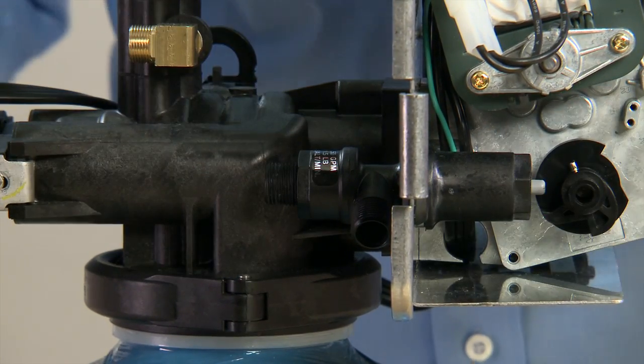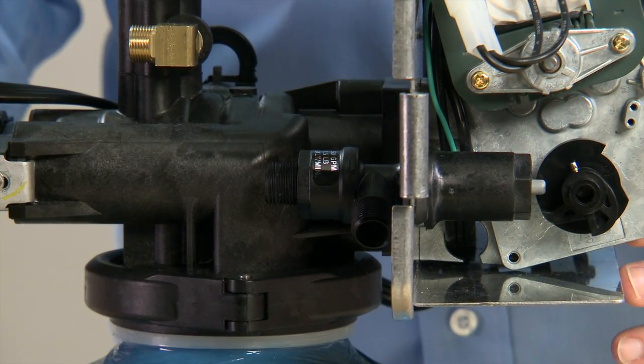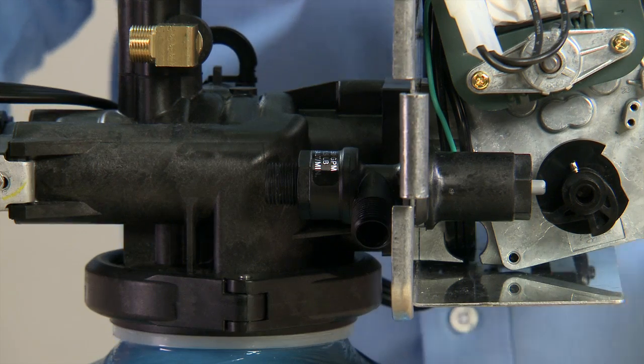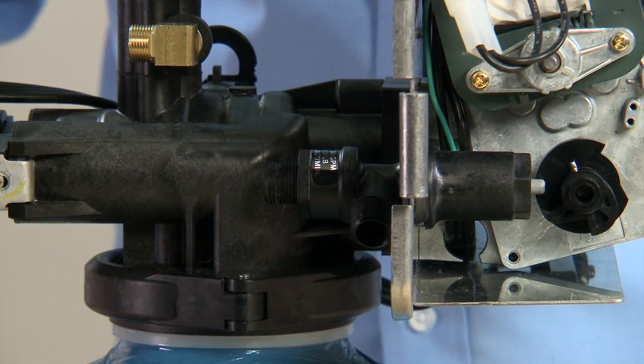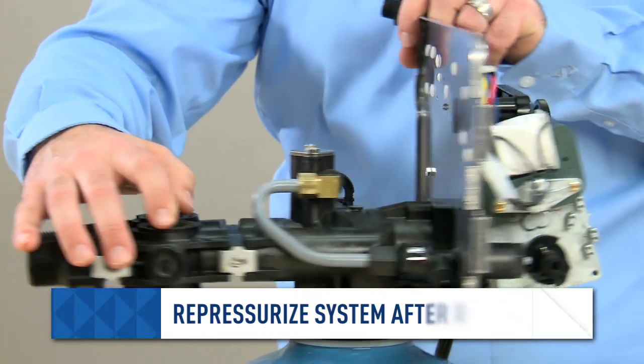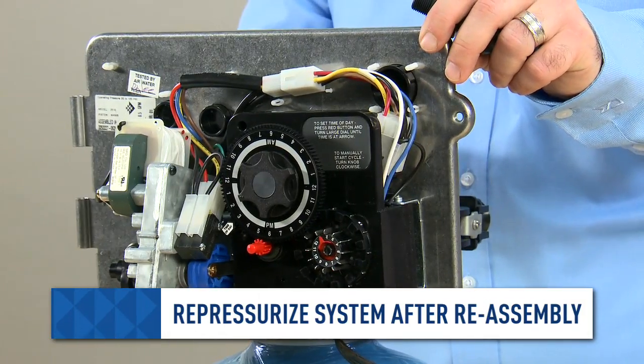Tighten all connections and make sure everything is airtight. Since these are flare connections, no plumber's tape should be used. You can then re-pressurize and test your progress.